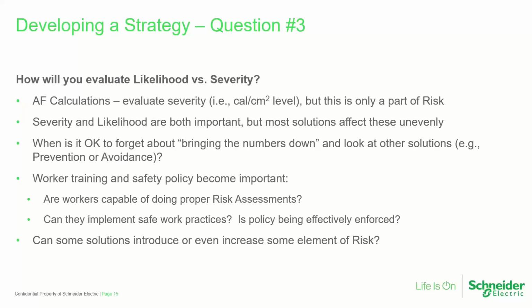Question number 3, how do you evaluate likelihood of occurrence versus severity? And we talked about this with some of those solution categories. Some would reduce the chance that an arc flash could occur. Others would reduce the calories per centimeter squared level. Typically the solutions don't affect both at the same time, or at least not to the same degree.